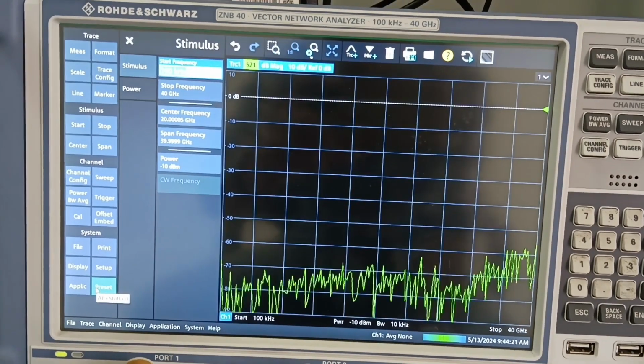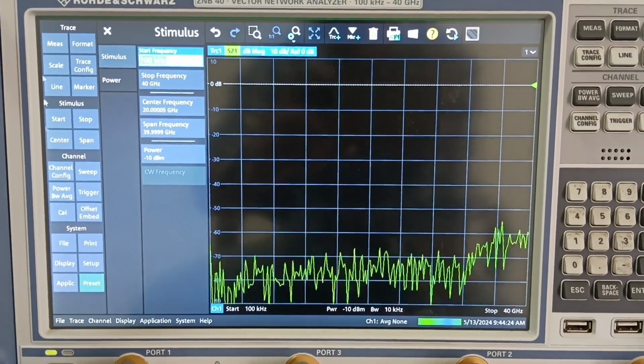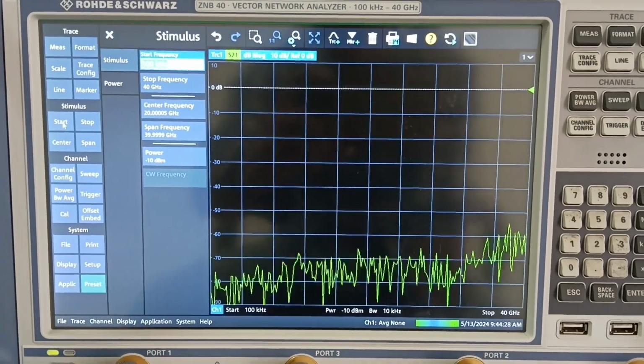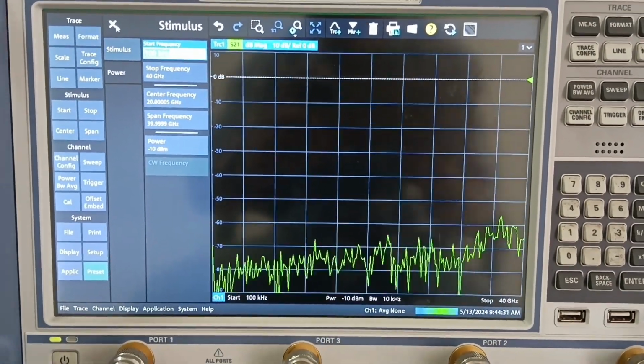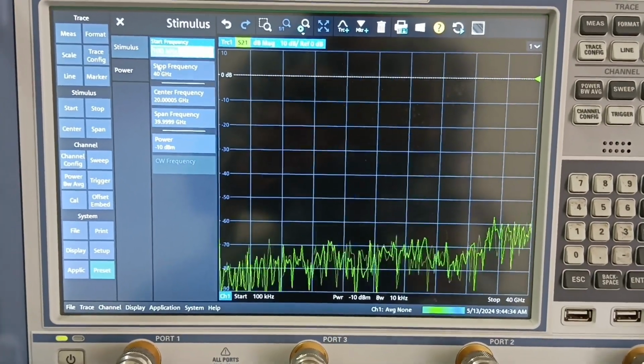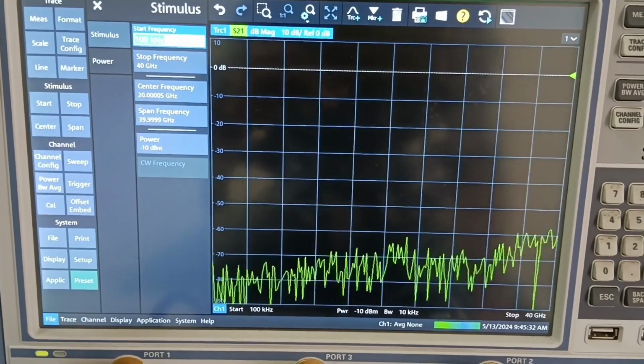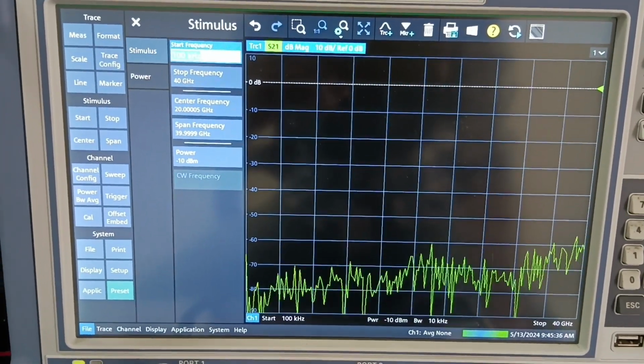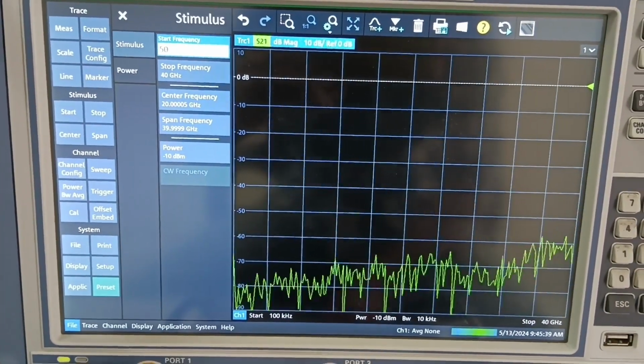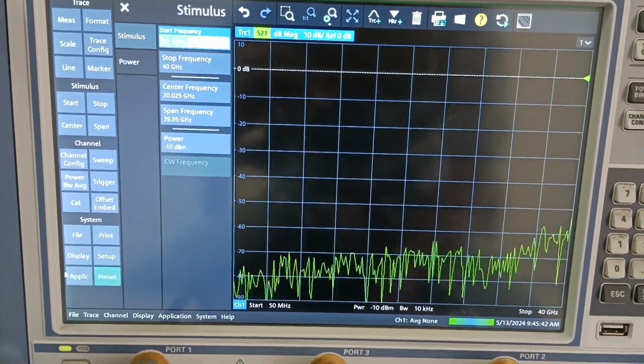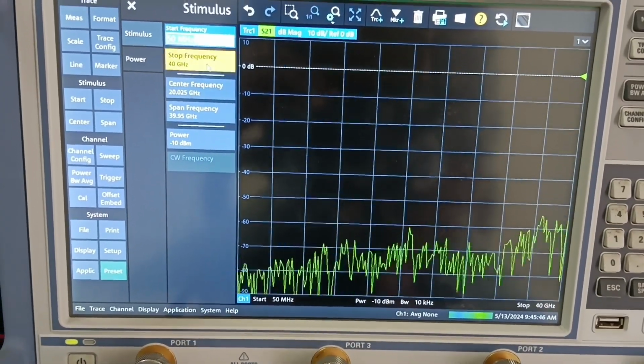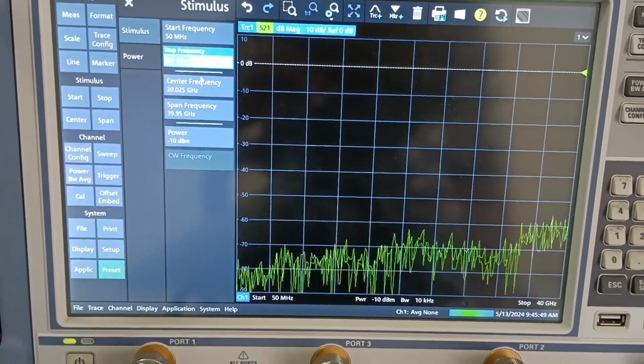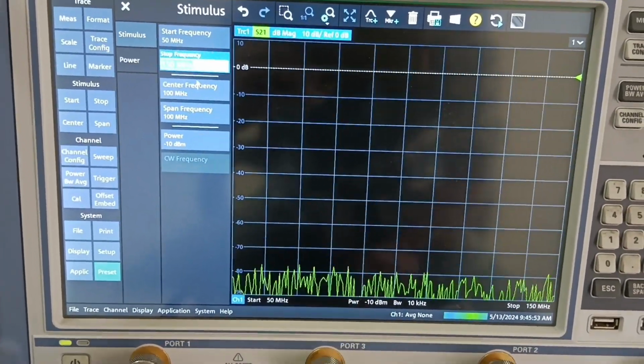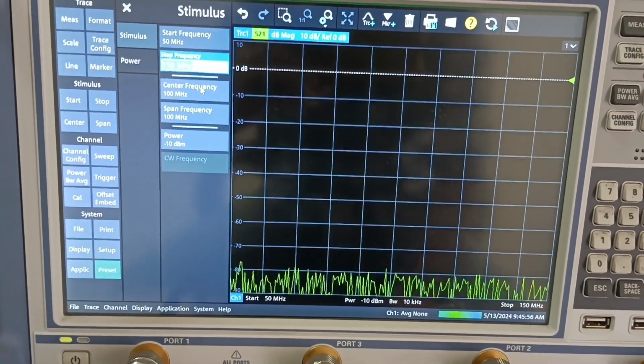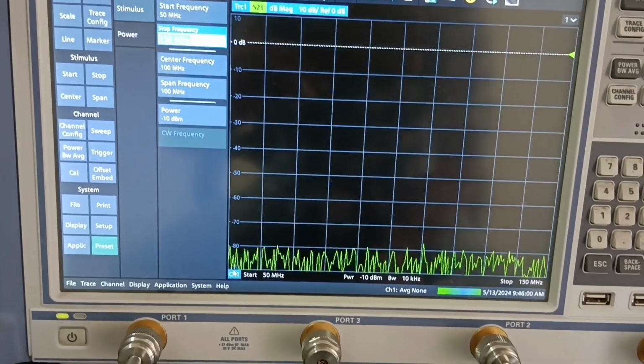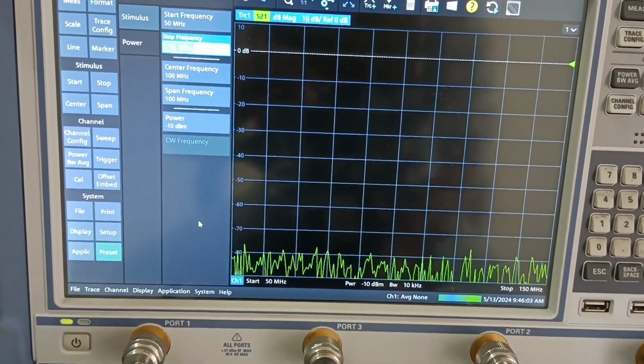So coming to the VNA, first of all we need to do the preset. That means it will be completely empty and it will start from the starting point onwards. Then we'll press the start button, and at that time it will show the start frequency, stop frequency and center frequency. First of all we need to feed the start frequency as per our requirement. Then after completing the start frequency, you will go for the stop frequency. So within the impedance bandwidth you need to feed the start and stop. Then the center frequency it will automatically detect and calculate. So once it is over, then we'll go for the next step.